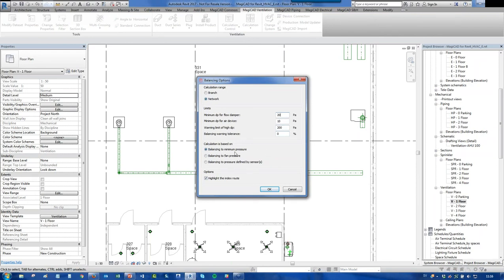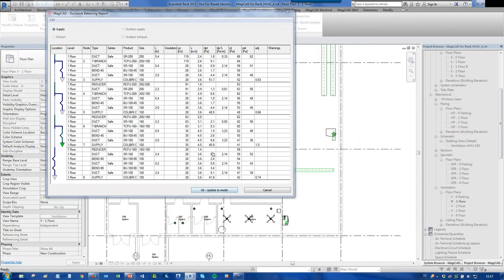We can balance to minimum pressure, which is the option I'm going to use now, but we can also balance to a given fan pressure, coming from a smart component, a manufacturer-specific component with built-in data, or balance according to some predefined sensors. If it doesn't have any of those, we just input the data ourselves. I click OK, select my duct system, and now you can see I have a little bit more data.